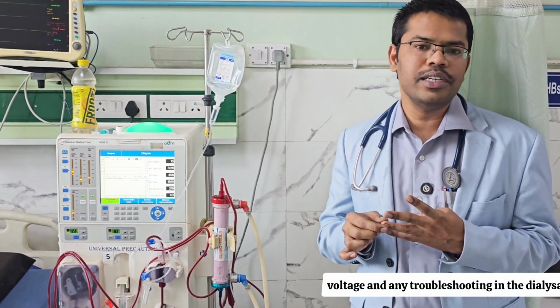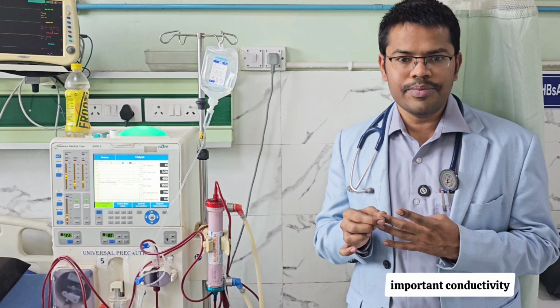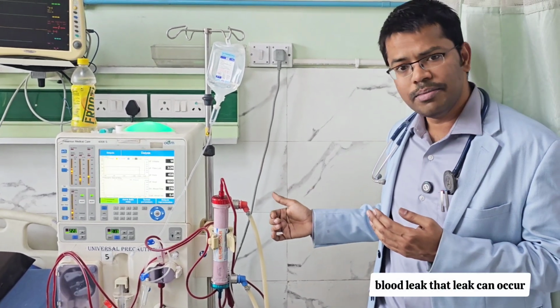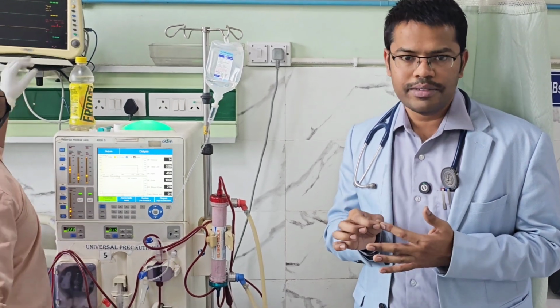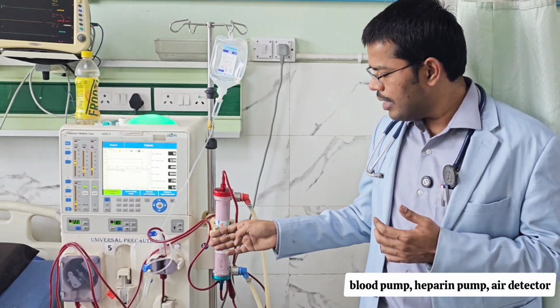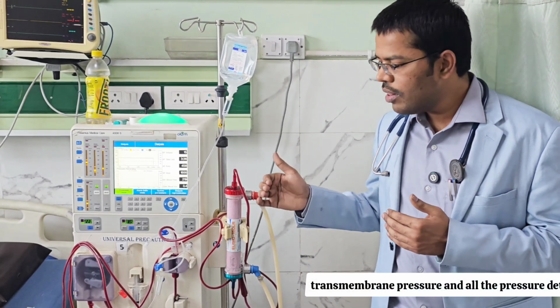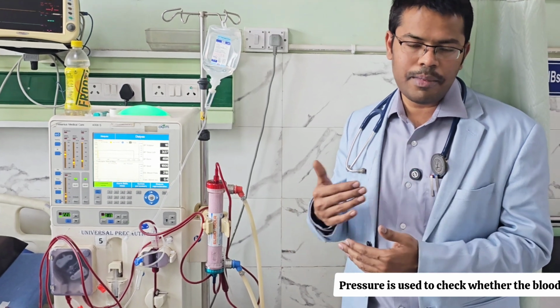So here I have given you the summary of the alarms, the alarms in the dialysis machine and for the patients undergoing dialysis. To conclude the video, you can classify four alarms: patient vital related, general alarms, dialysate circuit alarms, and blood circuit alarms. In the patient vital, BP and pulse. In the general, voltage and any troubleshooting. In the dialysate, the important ones are conductivity, temperature and blood leak. Three. In the blood circuit, five: pressure, blood pump, heparin pump, air detector, and transmembrane pressure. Pressure is used to check whether the blood flow to the patient or blood supply from the patient is good or not. So this concludes the video. Bye-bye.